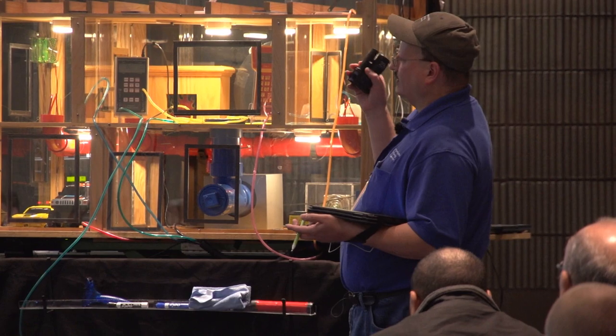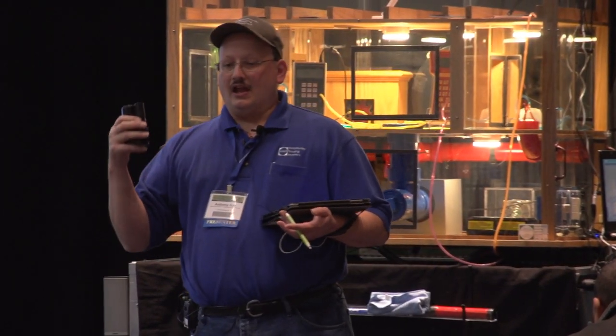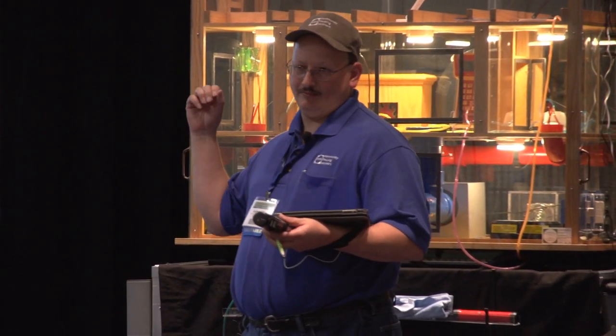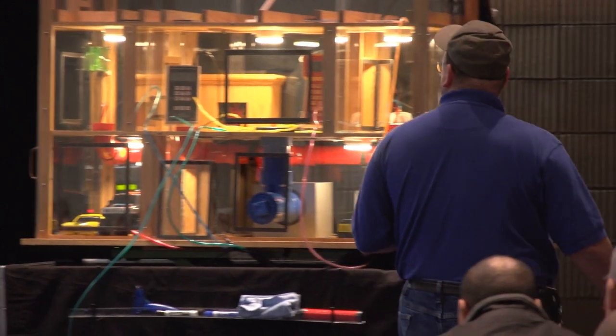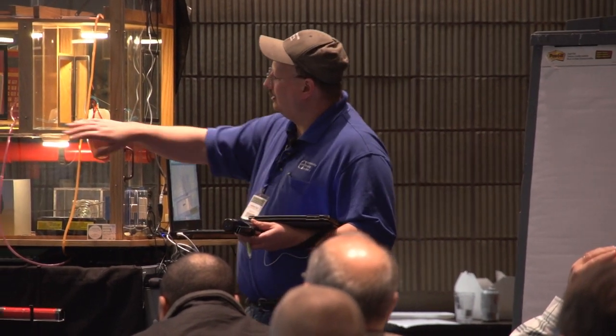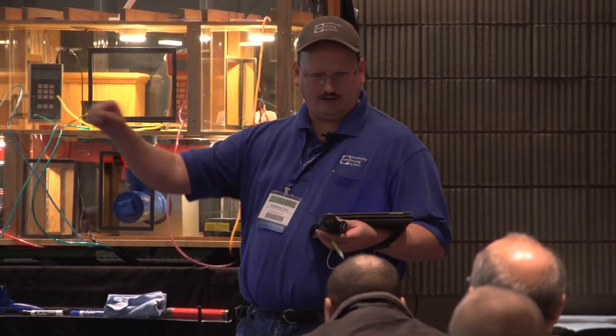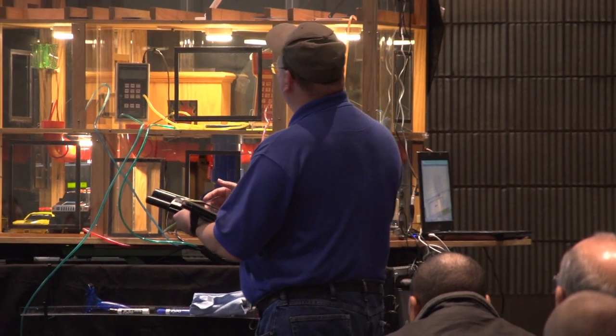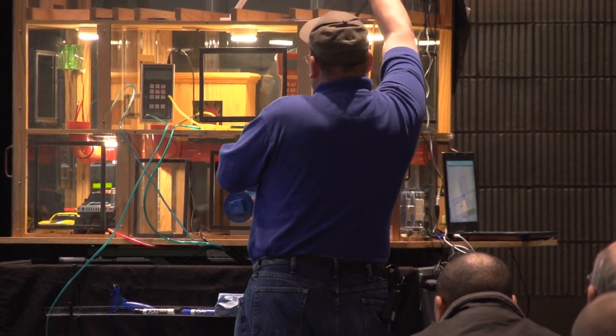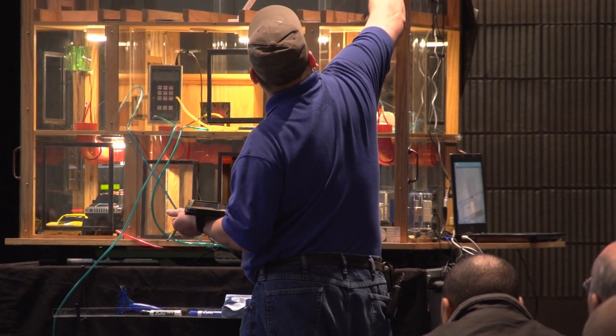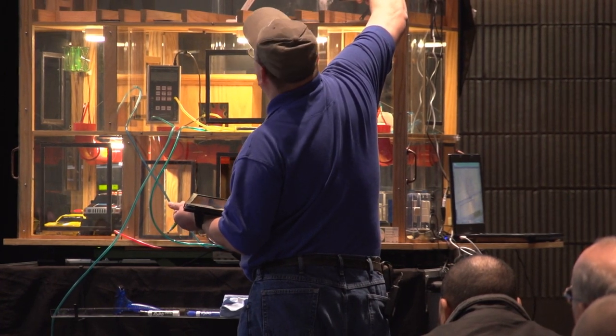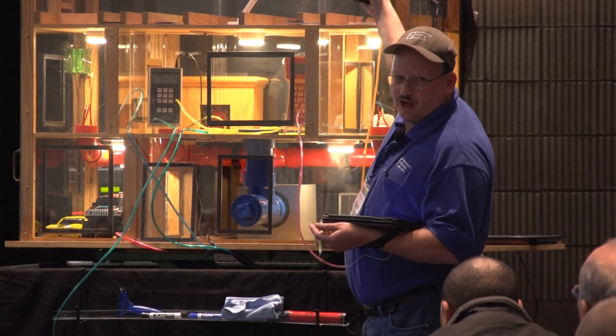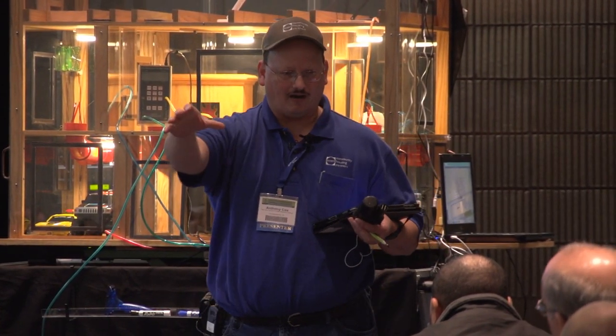What we'll also do is this, from the attic. When you're running the blower door and you have a smoke pencil in the attic, most of the time you depressurize. Is that right? Most of you folks depressurize? So if you're depressurizing, that means you're sucking air out with the blower door, right? And so if I turn the blower door on, for instance, I'll turn it on just a little bit. So now I've got a negative pressure in the house. My blower door's on, right? And I've still got this leak into the attic, and it may want to pull the air down into the house. Let's see if it'll do that. See if I can get a little smoke going on here. But it's actually going down in now, because the fan's sucking air out, right? And anywhere there's a hole to the outside, it's going to bring air in.